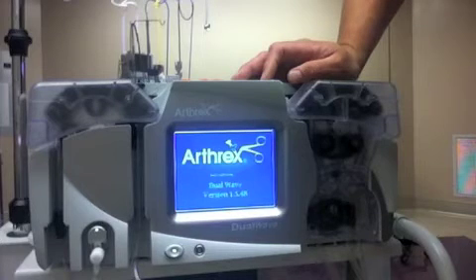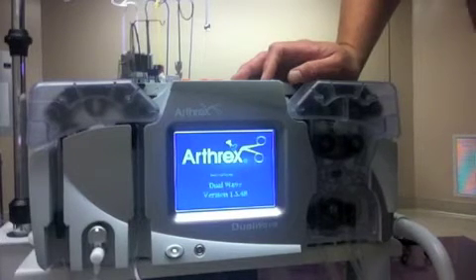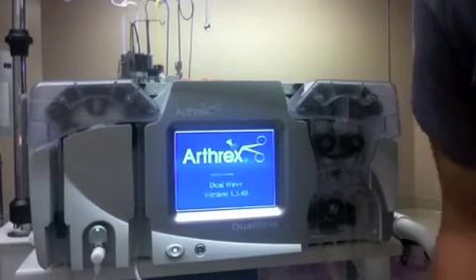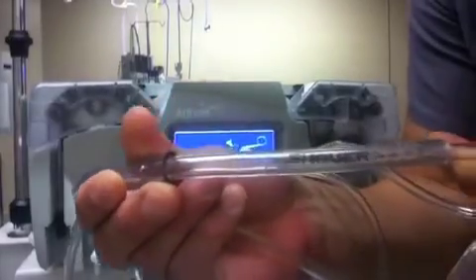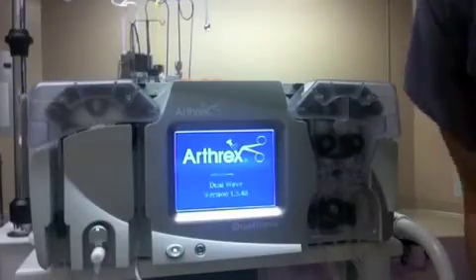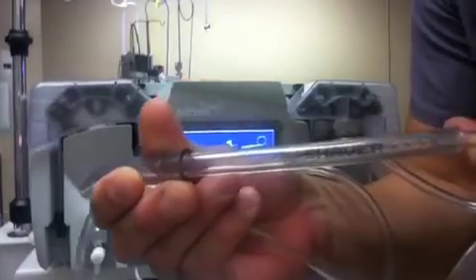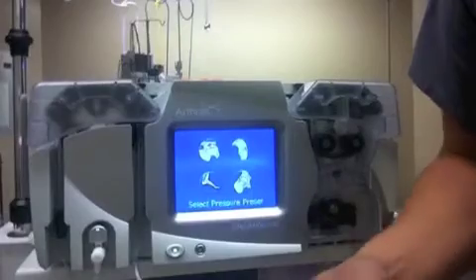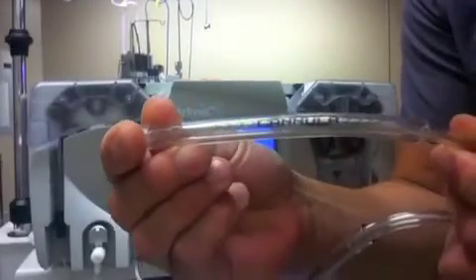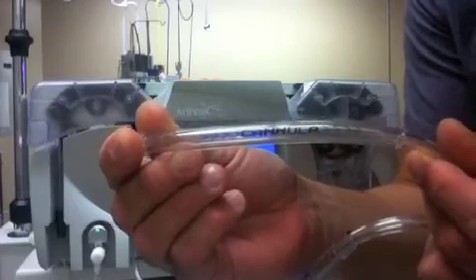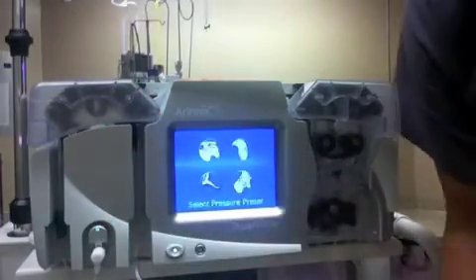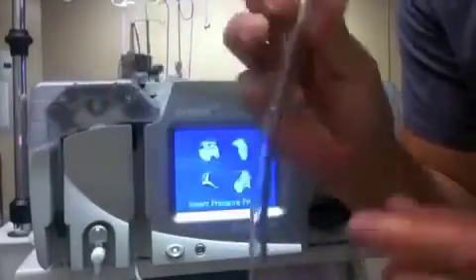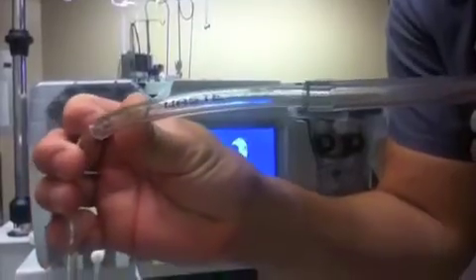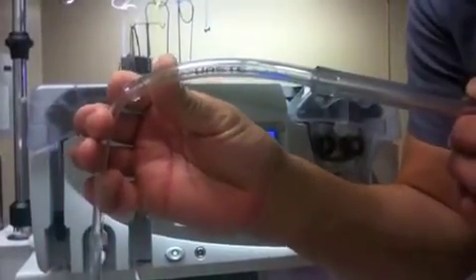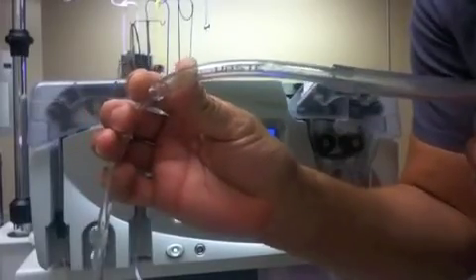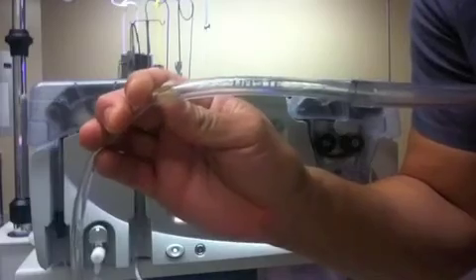On the surgical side or sterile field, to make sure it works properly, just make sure the proper tubes are connected to the proper place. In other words, the shaver line, I don't know if you can read that, needs to go to shaver. The cannula line needs to go to either the outflow on your scope sheath or ideally a separate portal with an outflow cannula. And your waste line needs to go out of the sterile field and needs to be placed either into a kick bucket, or it can go into a Neptune with the suction turned way down, as suction on this waste line is not a feature, in fact can be detrimental if the suction is too high.